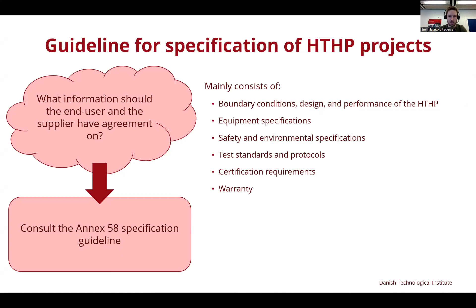And you could, as the supplier, calculate your expected performance for a set single design point. So for a given source temperature and a given sink temperature and a given flow rate on each side, you promise a certain performance. But you will find in reality that once the heat pump is installed, it's very unlikely to hit exactly these design conditions.